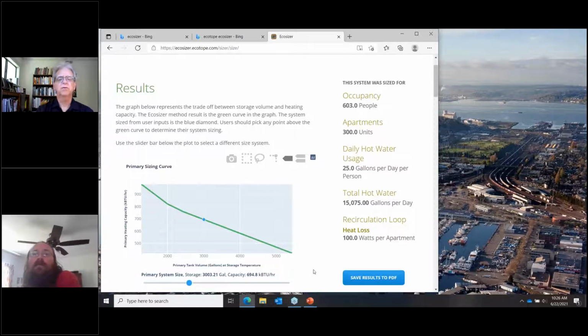You had some advice about this, Chris. Yeah, well, one obvious thing is that note that the y-axis doesn't go to 0, right? There's a threshold. Looks like maybe about 5,500 or so gallons, that amount of heat pump. If you slide all the way to the right real quick and see what that maxes out to be, the little blue grabber at the bottom. See that thing? There you go. Yeah, so that's telling you with 419 MBH worth of heat pump, you don't want to go more than 5,400 gallons. If you do, it's potentially not going to re-inventory. So just hammering that point home. Make sure you honor that balance.